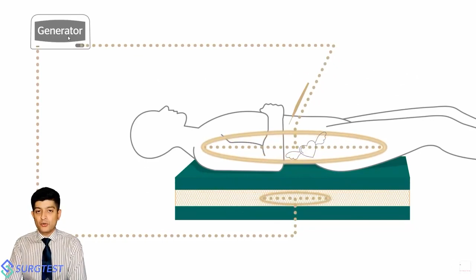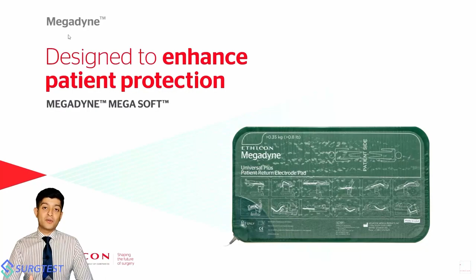These pads are extremely large, about 3 by 2 feet in size. That's feet, not inches. As a result, these can be placed under the entire patient on the OT table. And as I said, the capacitance, or rather the amount of energy that can be delivered, is a direct function of how much area is in contact. As the amount of area keeps reducing, the amount of energy that can be delivered to the tissues will keep on reducing. In contrast with a standard dispersive electrode, where there's actual flow of electrons within the circuit, if you reduce the amount of contact, then you have a higher current density with a higher chance of injury.